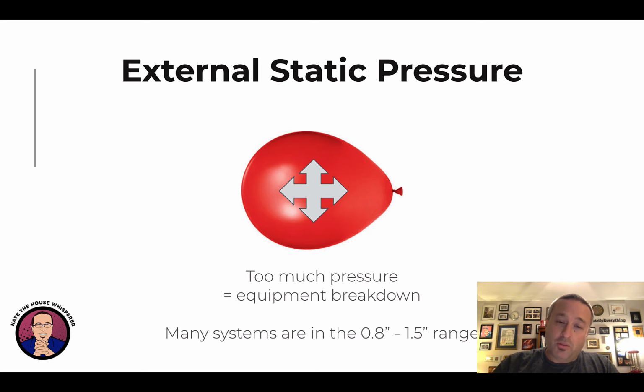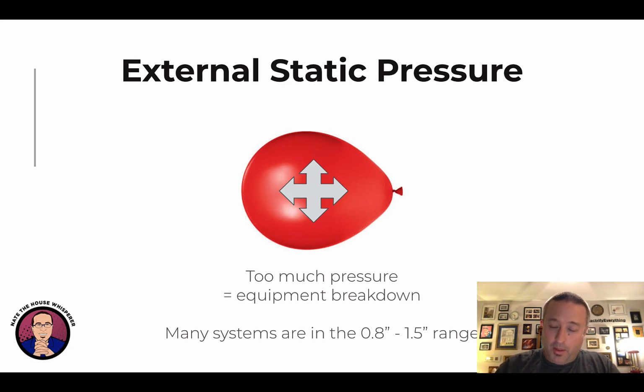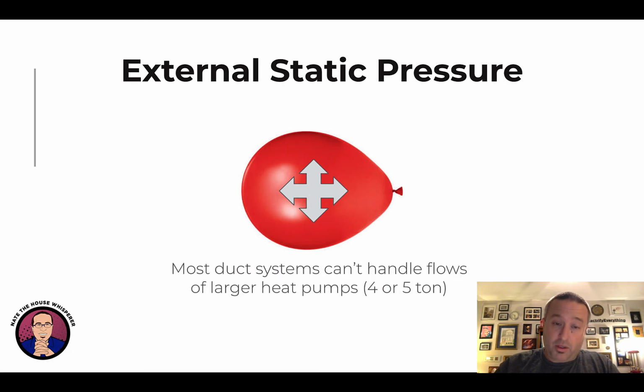So if you have too much pressure, again, you're going to get equipment breakdown. And the curse here is most systems that I have tested and that I hear my HVAC brethren testing land in the 0.8 to 1.5 inch range, so 3 times what they're supposed to have. Most manufacturers stop even putting any kind of ratings on how much airflow that they will have somewhere in the 0.8 to 1 inch range. So if you're at 1.5 inch, I mean, that's high blood pressure. That sucker's going to blow. And I've seen failures pretty early.